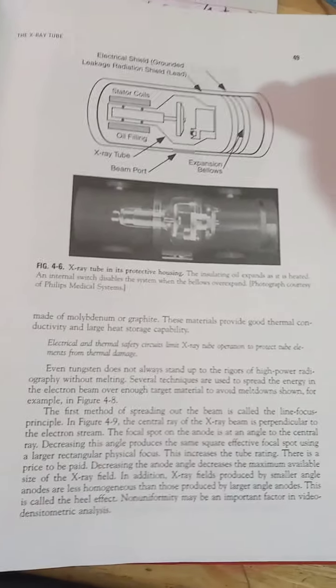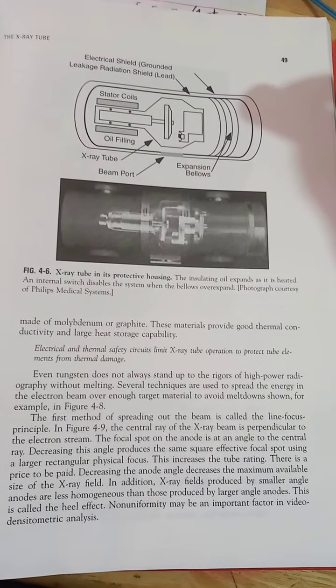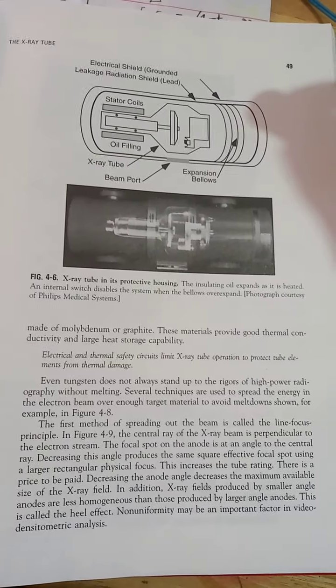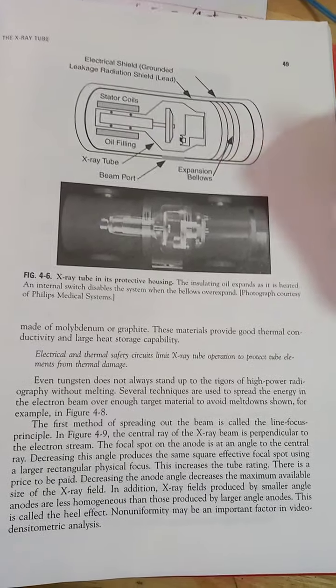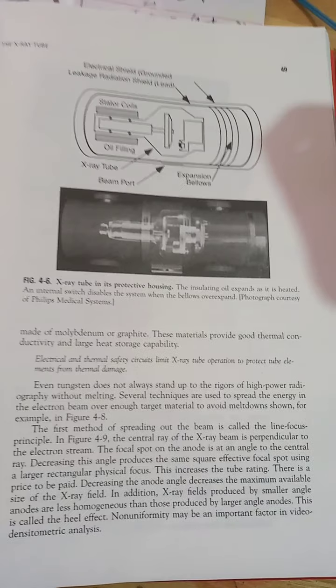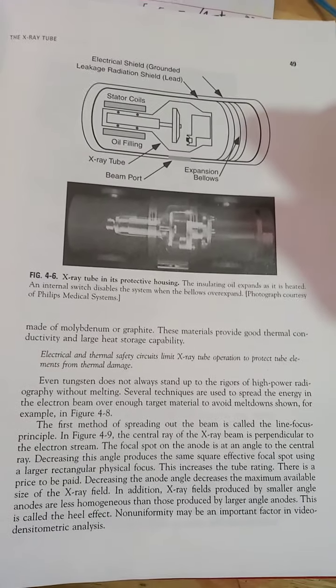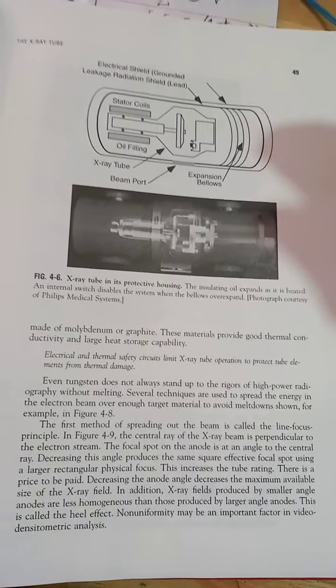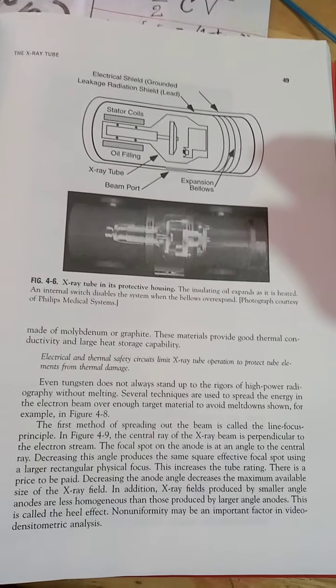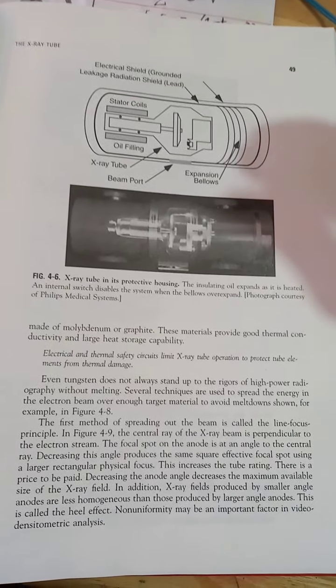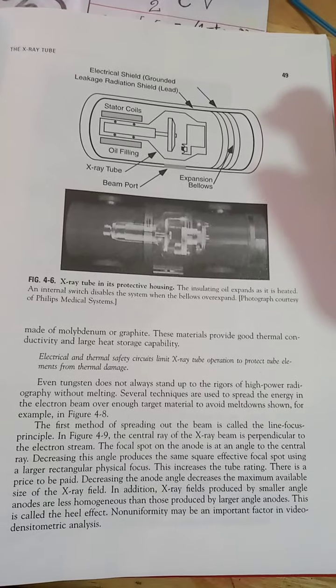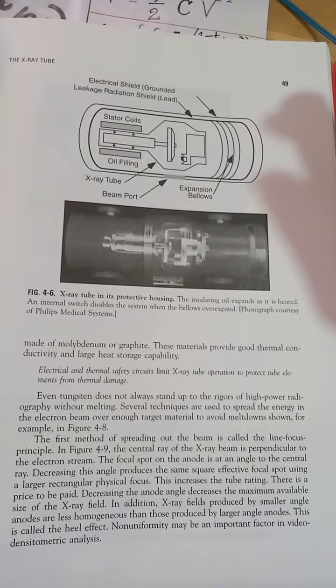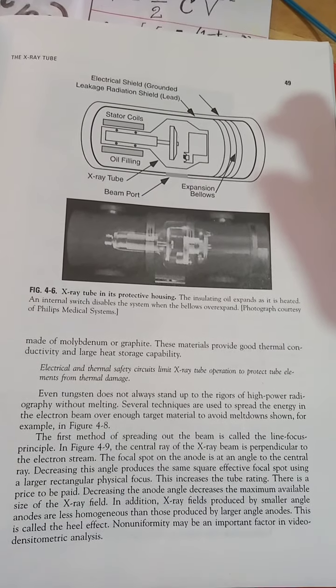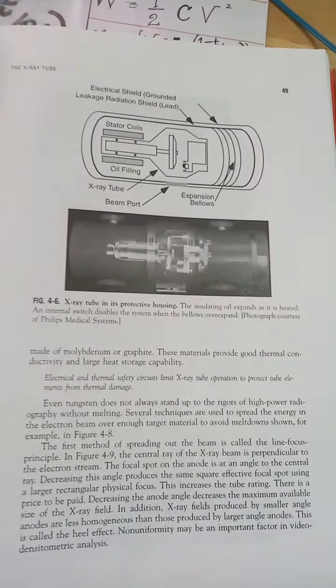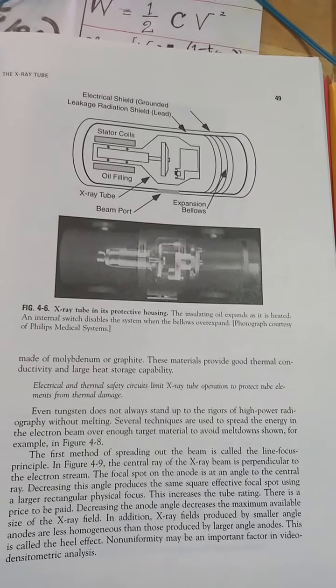The first method of spreading out the beam is called the line focus principle. In the figure, which is not available on this page due to poor organization, the central ray of the X-ray beam is perpendicular to the electron stream. The focal spot on the anode is at an angle to the central ray. Decreasing this angle produces the same square effective focal spot using a larger rectangular physical focus. This increases the tube rating.